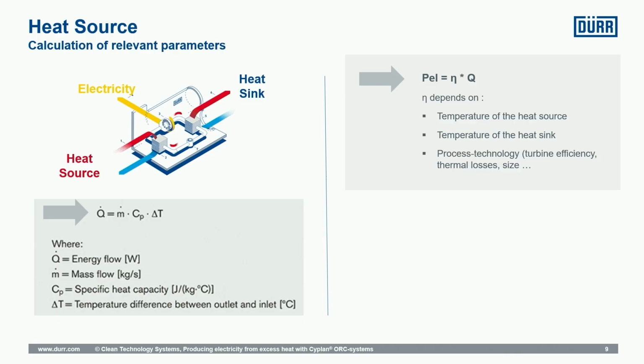So we have here some equations - what are the important parameters, and that clearly is the heat input. Q stands for heat or energy input, and that's just a multiplication of the mass flow, the specific heating value, and the temperature range - cooled down from what temperature to what other temperature. It may well be different whether you have water as the source of your thermal energy, or it's gas - then you are dealing with much higher volumes to have the same mass flow and the same energy in the end. And then the power, the electric power, is on the right-hand upper side - that's simply the outcome, determined by the electrical efficiency of the system.